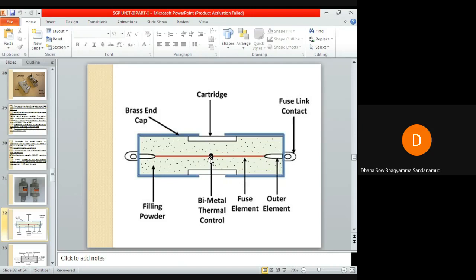So this arc will continue the fault current to flow from one phase line to the other phase line. So we have to quench the arc as quickly as possible. We have to extinguish the arc as quickly as possible. As soon as the fusing element melts, the silver material will be vaporized. This silver vapor will have a chemical reaction with the filling powder that will result in the formation of a high resistance substance which helps in quenching the arc.